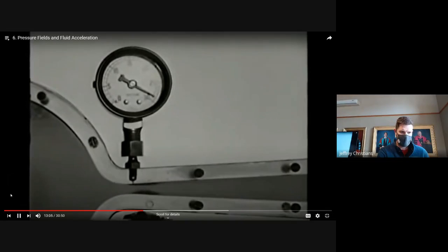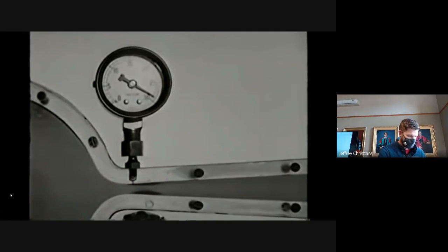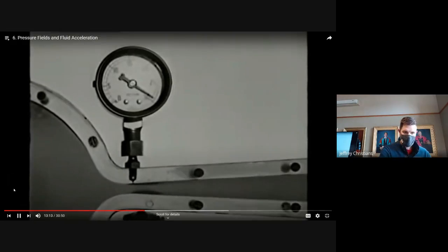And the subsequent collapse of the bubble, which you can hear, creates enormous stresses in the wall. Mechanical stresses owing to the implosive collapse of cavitation bubbles on a surface do great damage to hydraulic machinery.